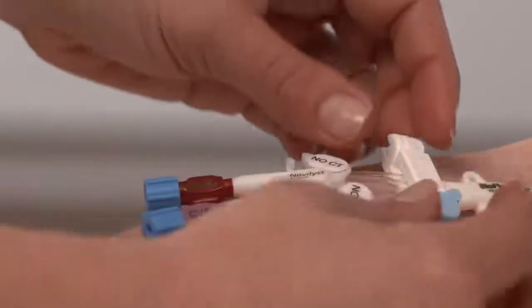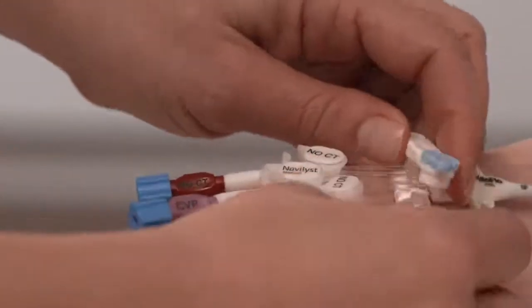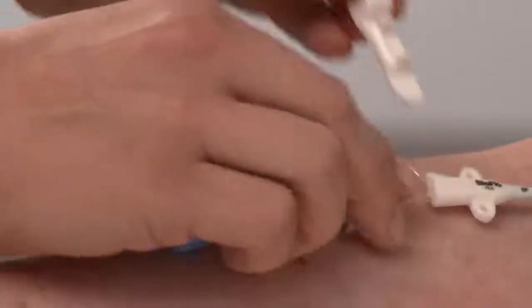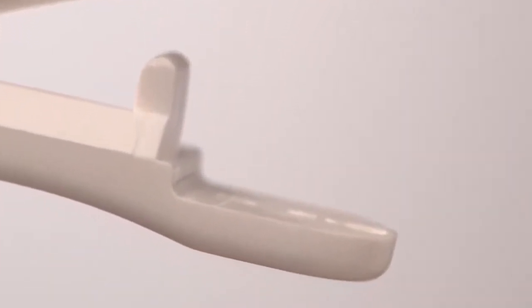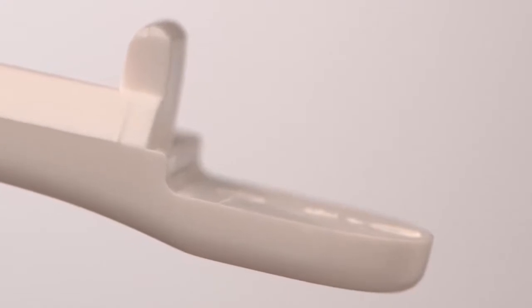Even a strong hand with a syringe cannot force fluid through the clamped line. To open the clamp, rotate the blue knob clockwise. When the knob is turned, the plastic hook, now captured inside the knob, is twisted off the bottom arm. This destroys the locking mechanism and the patient cannot relock the device. The destruction of the single-use locking mechanism clearly demonstrates that the patient has opened the clamp and strongly suggests tampering with the catheter has occurred.